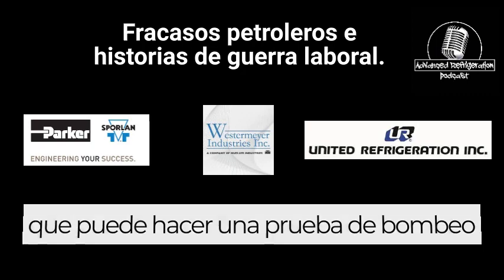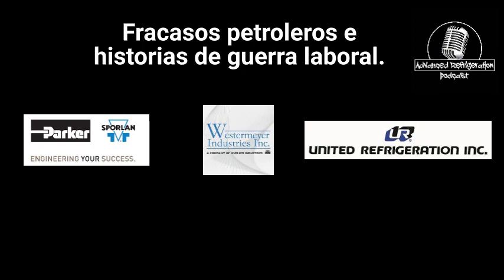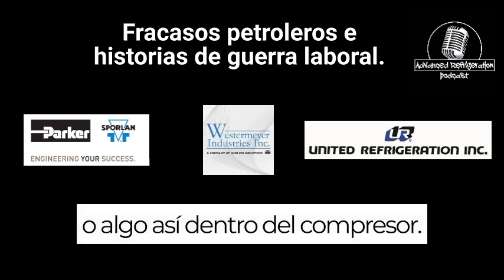At that point, you can do a pump down test and see what's actually wrong with that compressor, unless something is drastically wrong. It could be discharge valves or suction valves, or you could have dropped a piston or something like that inside the compressor.